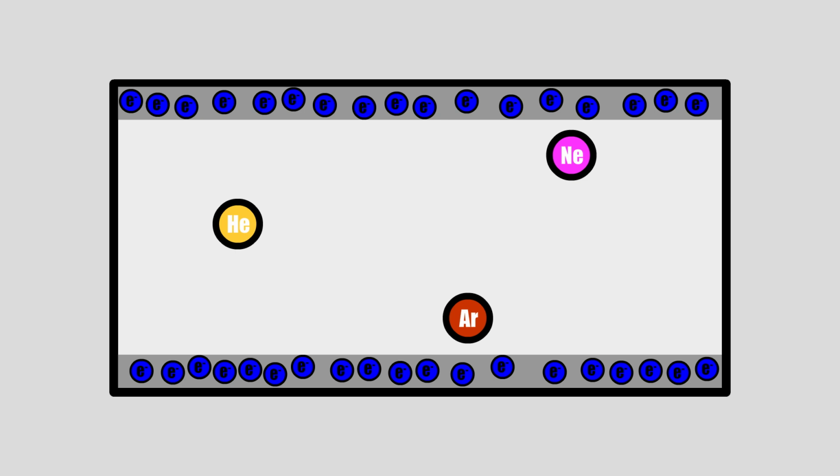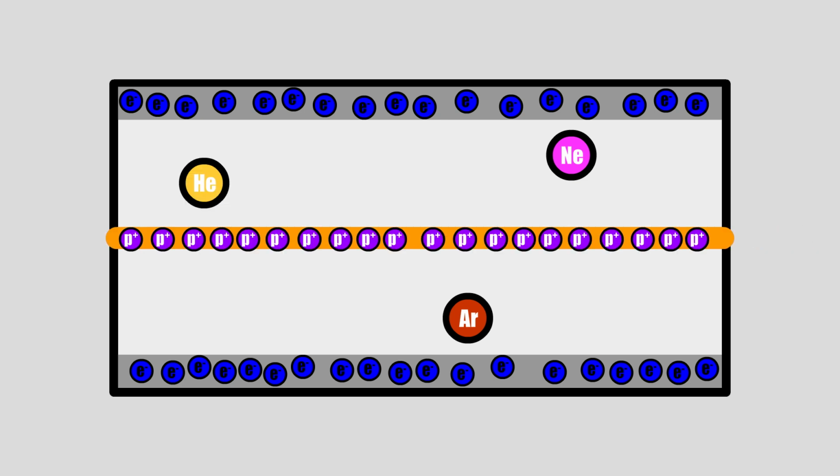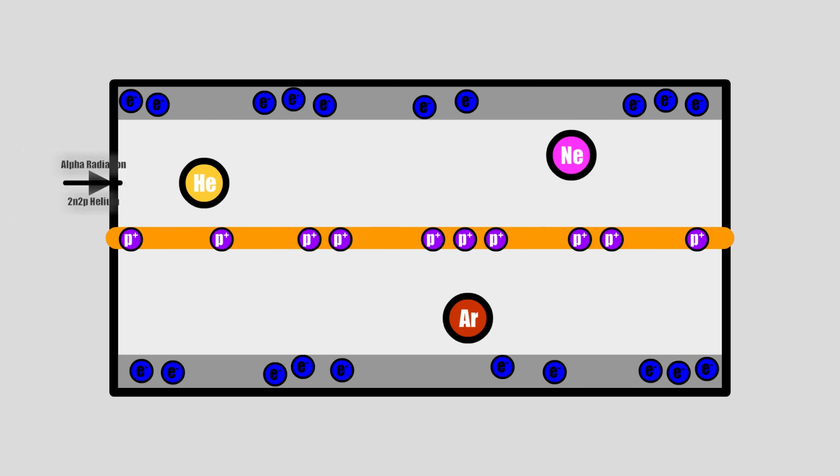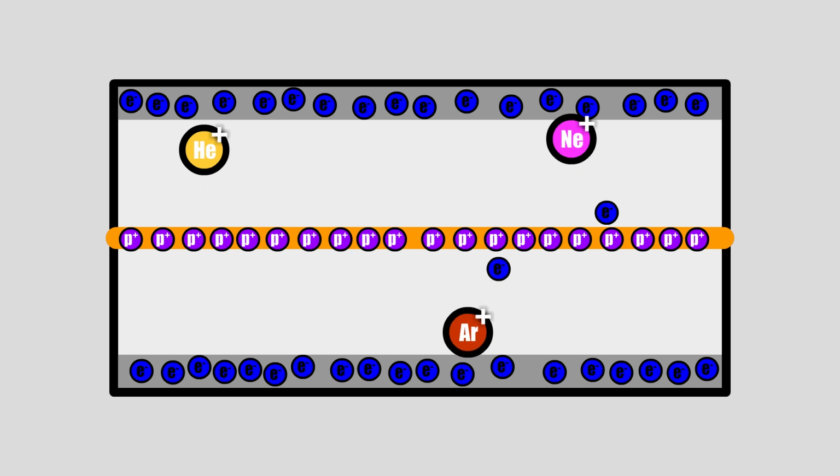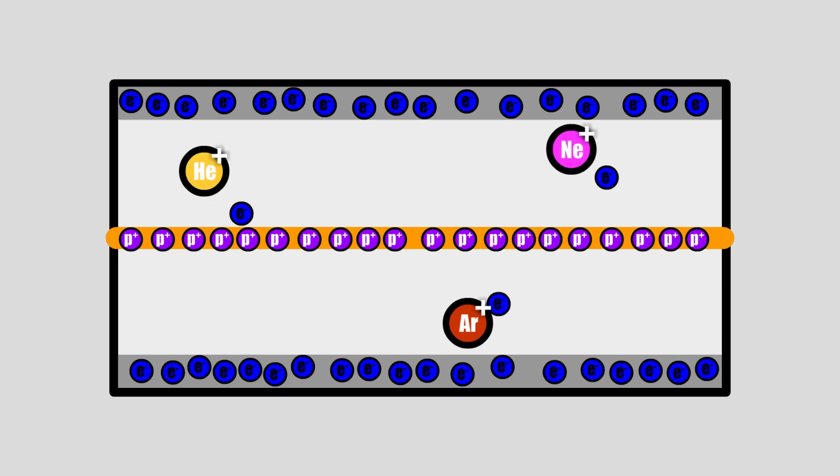To direct the electrons resulting from ionization, a positively charged rod is placed at the center. This voltage must be high because we want to detect every electron released through ionization. If the voltage is low, the probability of electrons recombining increases. However, the voltage should not be too high either. If it is, it may ionize the gas in the chamber by itself, resulting in faulty radiation measurements.